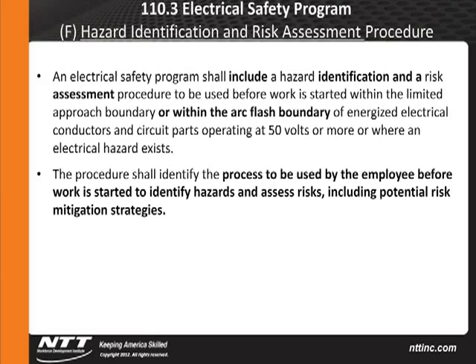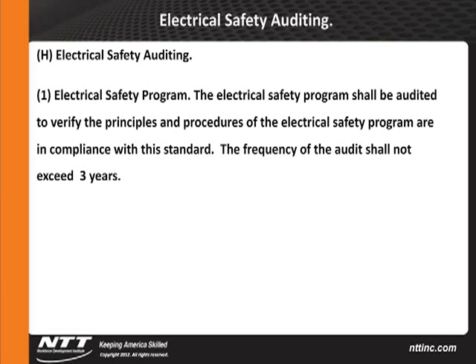Earlier on, as I said, one of the changes in there is an auditing requirement. It says electrical safety program. The electrical safety program shall be audited to verify the principles and procedures of the electrical safety program are in compliance with this standard. The frequency of the audit shall not exceed 3 years. So what are we going to be doing out there? What kind of program are you going to be putting together to have a qualified person audit the principles and procedures you have in place?